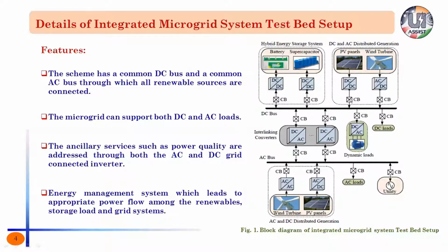This consists of both AC and DC type renewable energy sources, mainly a DC bus and an AC bus. The renewable sources will be connected at both the DC bus and the AC bus, and loads will also be connected to both DC and AC sides. Power exchange between the buses is handled by interlinking converters, and the storage system is connected to the DC side based on the application.